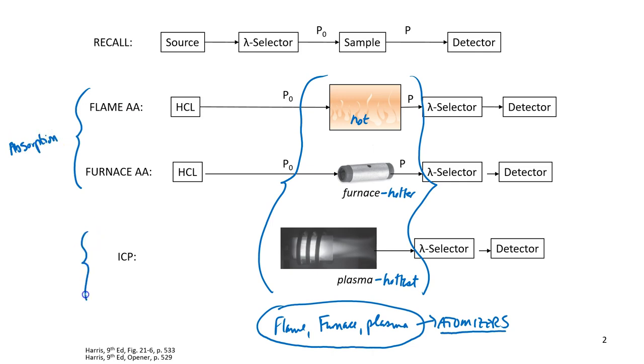And in ICP, we're measuring emission of radiation. So, remember, there was no light source here because the plasma is so hot. Not only does it function as an atomizer to atomize our sample, it's hot enough to promote our analyte to an excited electronic state, which I'll call our analyte X, and I'll use an asterisk to represent that it's electronically excited. As it relaxes back down to the ground state, back to X in the ground state, it releases a photon, and that is what is measured. That is the emission of radiation that you're measuring, so there is no source. The sample itself, if you will, is the source.